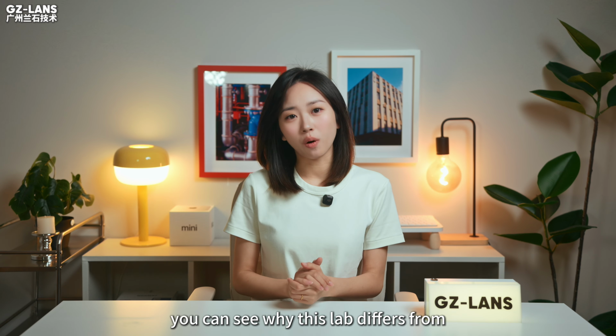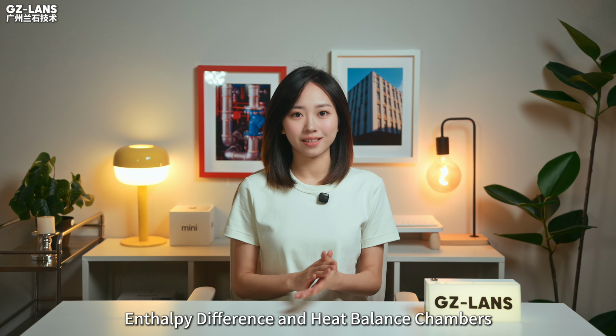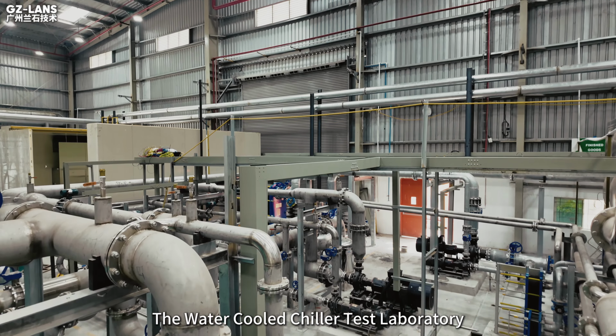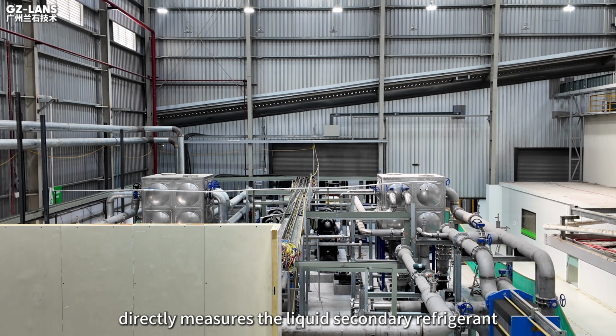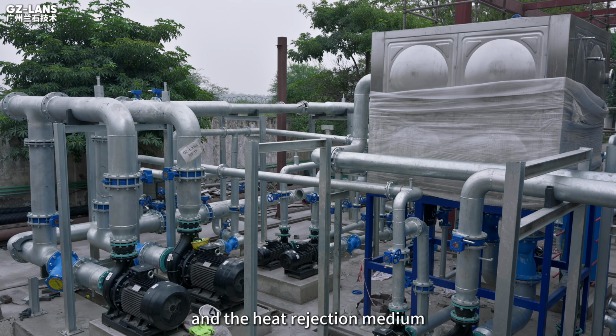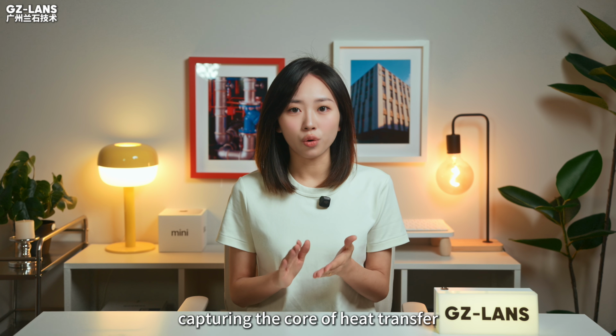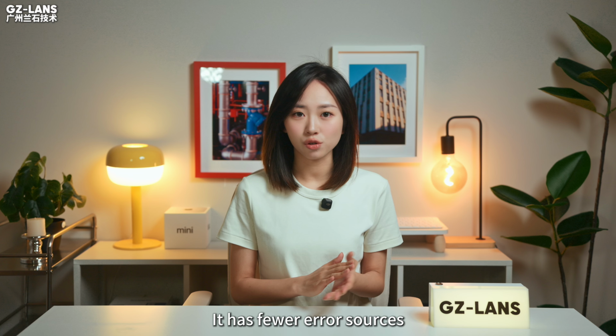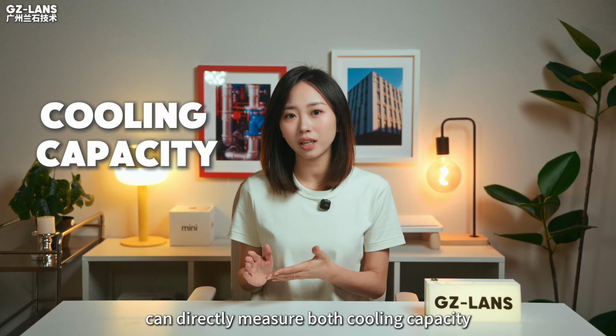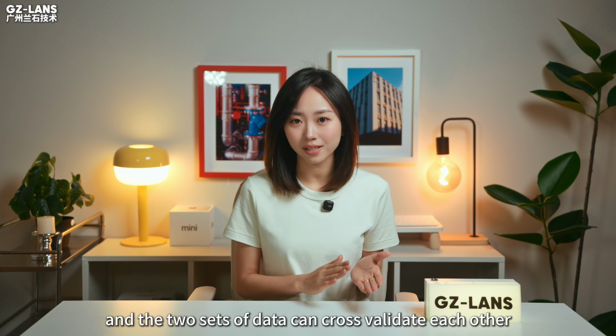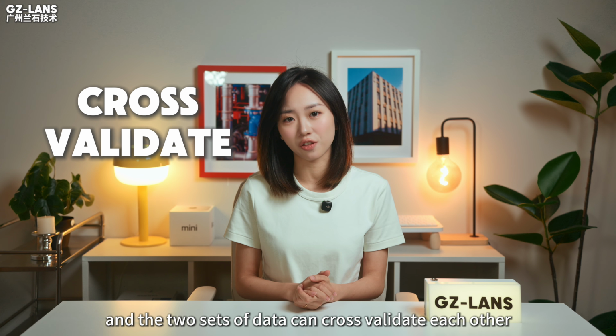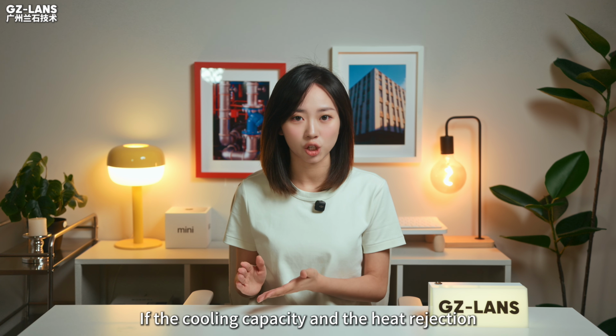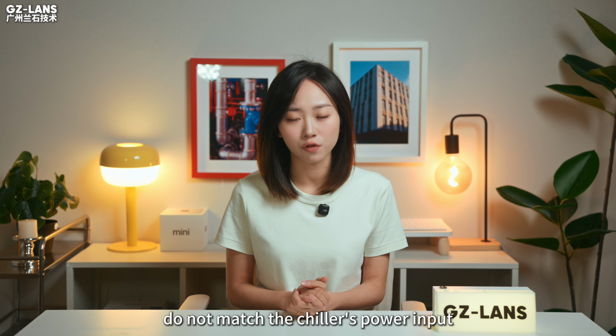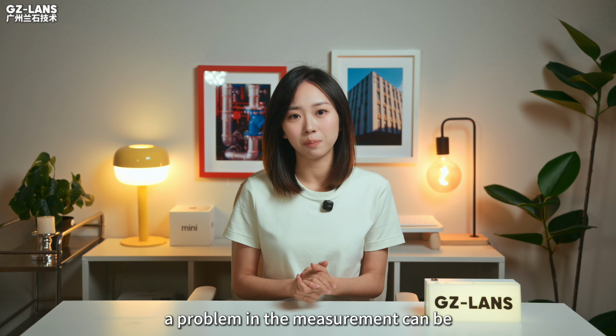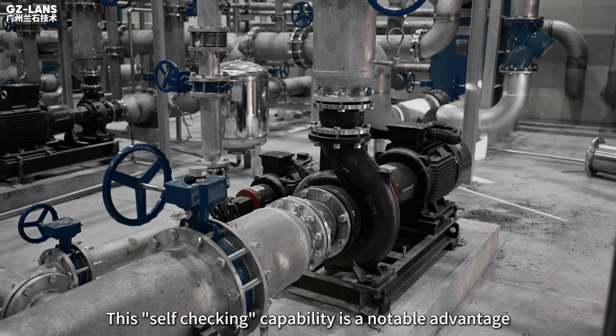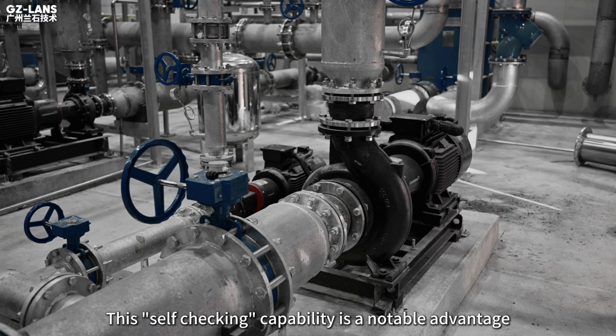From this, you can see why this lab differs from enthalpy difference and heat balance chambers. The water-cooled chiller test laboratory directly measures the liquid secondary refrigerant and the heat rejection medium, capturing the core of heat transfer. It has fewer error sources, can directly measure both cooling capacity and heat rejection, and the two sets of data can cross-validate each other. If the cooling capacity and the heat rejection do not match the chiller's power input, a problem in the measurement can be immediately identified. This self-checking capability is a notable advantage.